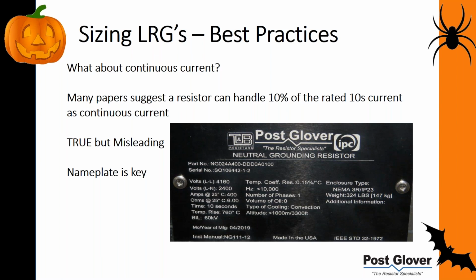If you truly need more than 10 amps of current, I would try to get it on the nameplate. Now, you may say, well, I'm only going to be using this for 2 seconds or less, so I'm pretty sure this will be fine. I have 30 amps of continuous current, it's going to have a certain degrees C rise, and I'm only using this for 2 seconds when it's rated for 10 seconds, so I should be good.